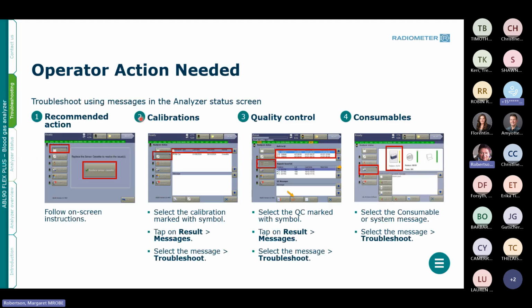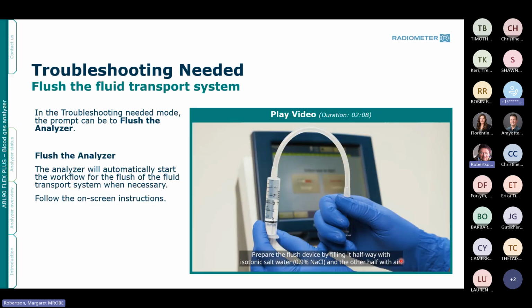In the first slide, we're talking about troubleshooting the analyzer based on a status screen. So we're looking at what's come up here. The recommended action is replacing a sensor cassette. Looking at the second part of this, in calibrations, we would pull the calibration up, pick up the result here, and again, you can select the troubleshooting message. Same thing here, we can do the selected QC, tap the results, tap troubleshooting, and this will also give you a determination on what needs to be done. And then the same thing with consumables. Everything is very straightforward and performed very easily with the analyzer. I think you'll find that as you start working with it.